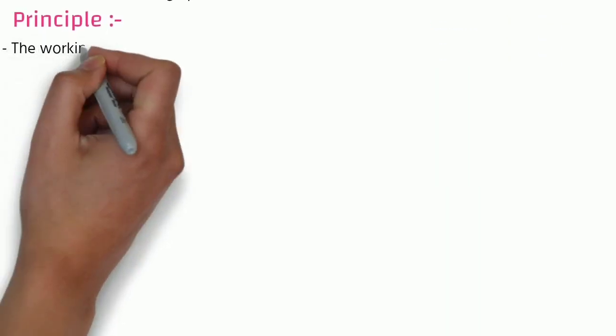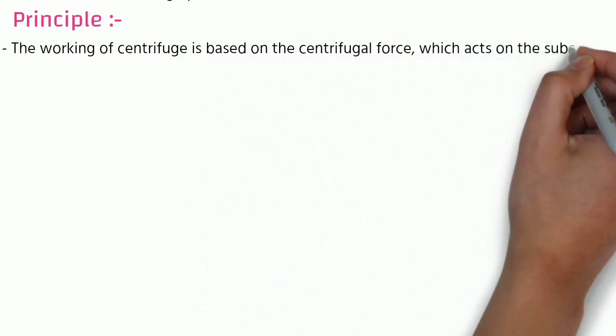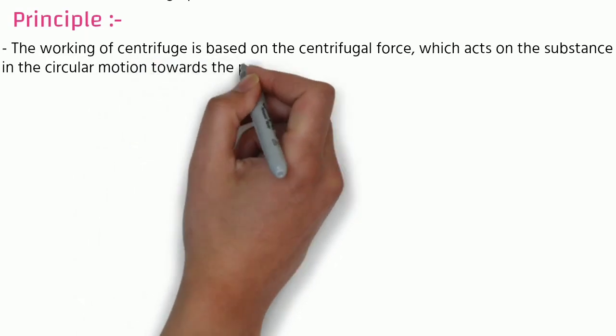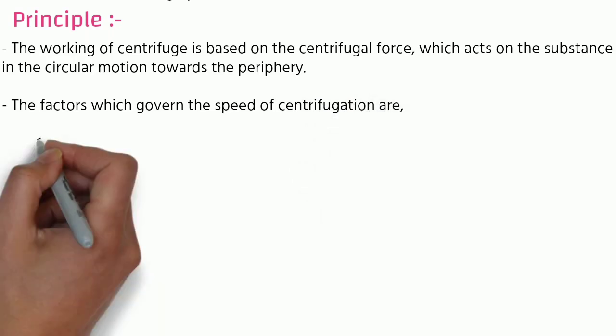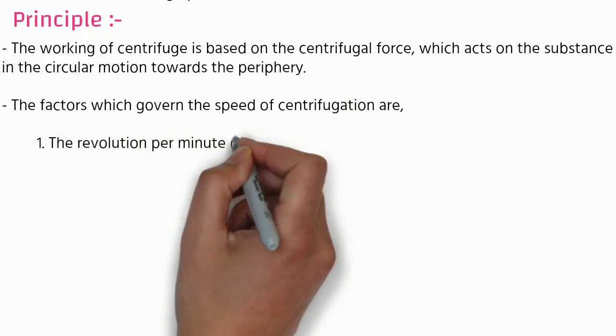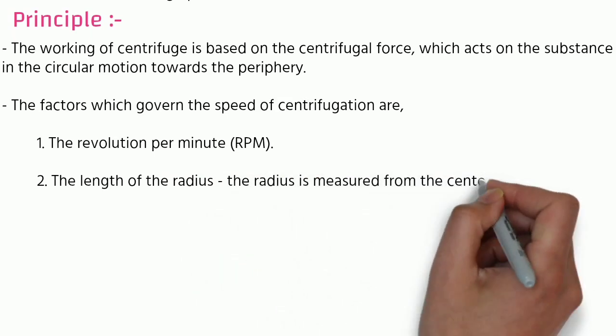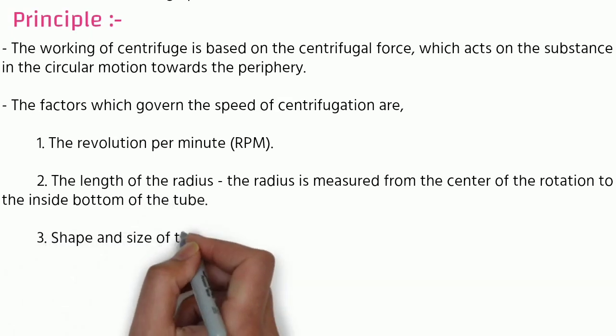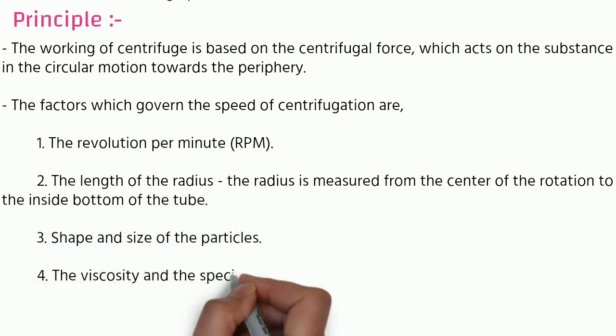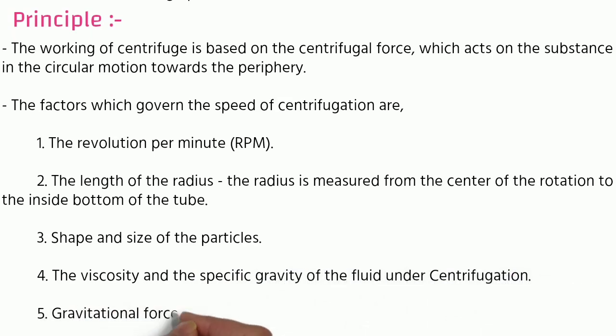The working principle of centrifugation is based on centrifugal force, which acts on a substance in circular motion towards the periphery. The factors that govern the speed of centrifugation are: revolution per minute (RPM), the length of the radius — measured from the center of rotation to the inside bottom of the tubes — the shape and size of the particles, the viscosity and specific gravity of the fluid, and gravitational force acting on the particles.